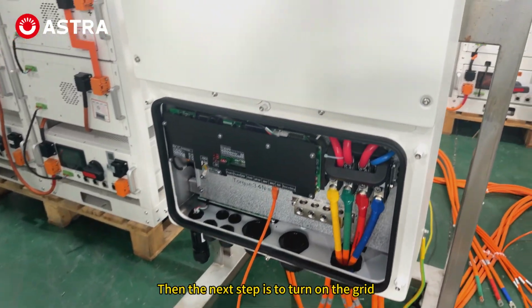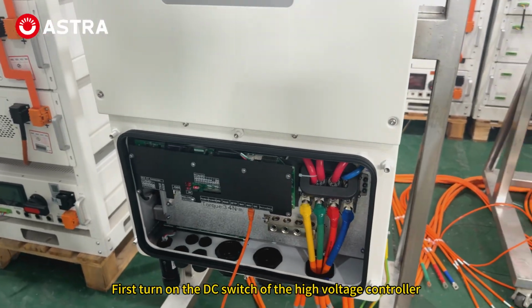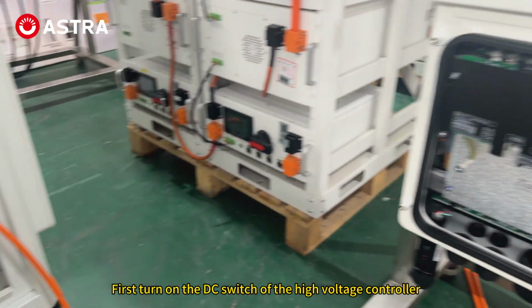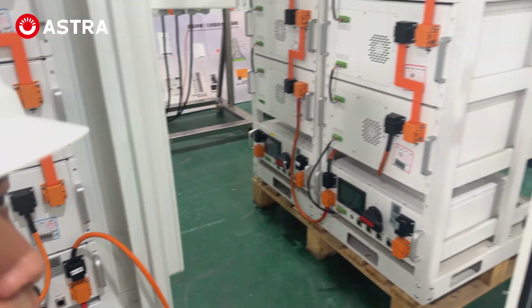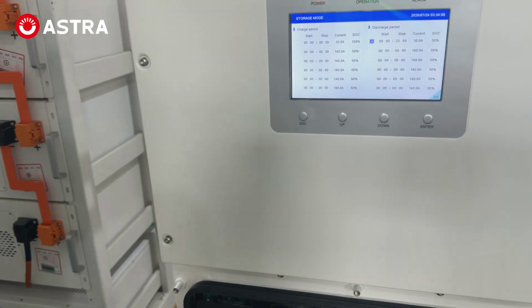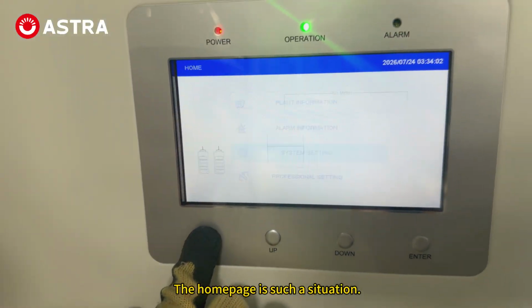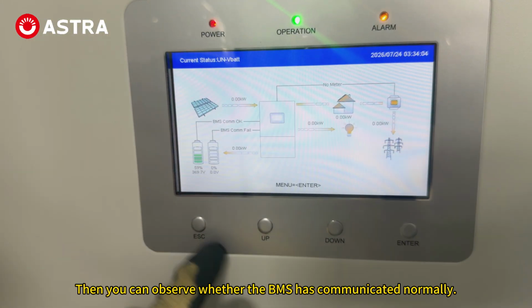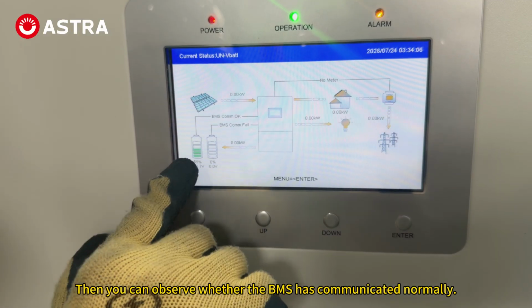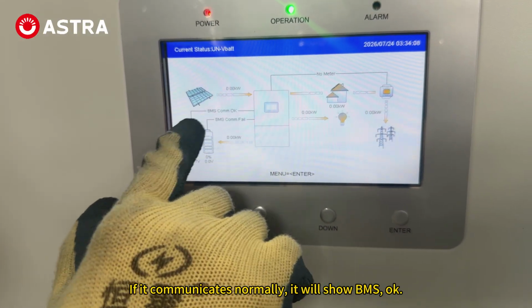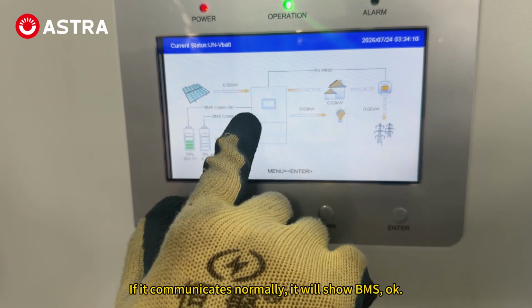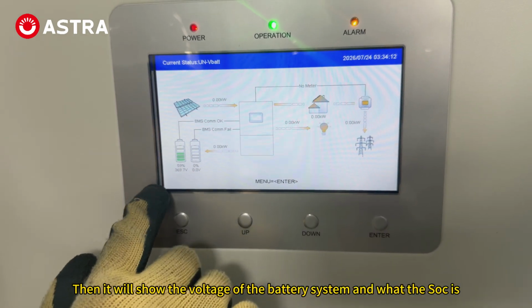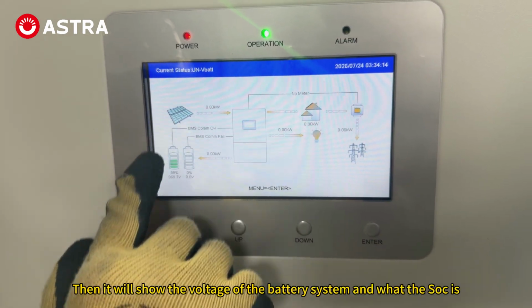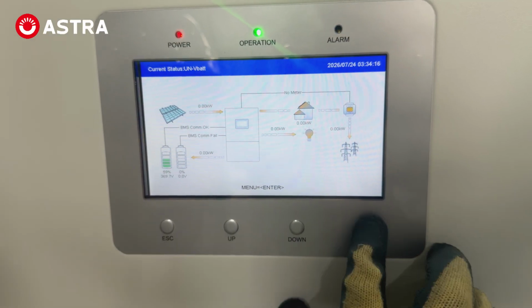Then the next step is to turn on the grid. First turn on the DC switch of the high voltage controller. And look at the screen. The home page is such a situation. Then you can observe whether the BMS has communicated normally. If it communicates normally, it will show BMS, OK. Then it will show the voltage of the battery system and what the SOC is.